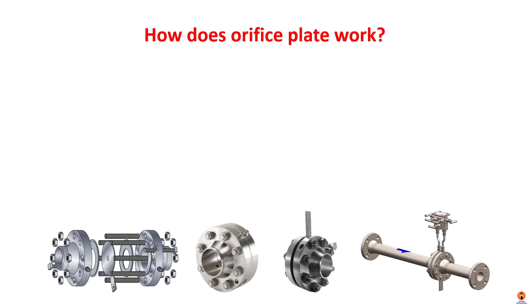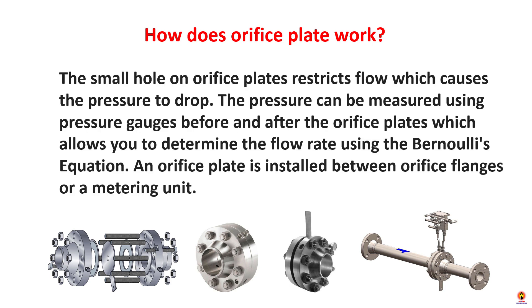How does an orifice plate work? The small hole in an orifice plate restricts flow, which causes the pressure to drop. The pressure can be measured using pressure taps before and after the orifice plate, which allows you to determine the flow rate using Bernoulli's equation. An orifice plate is installed between orifice flanges or a metering unit.